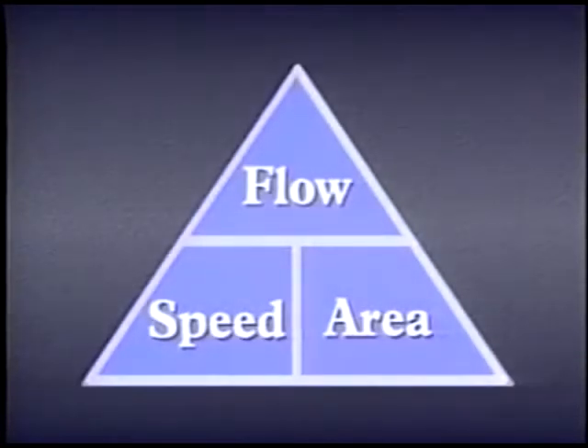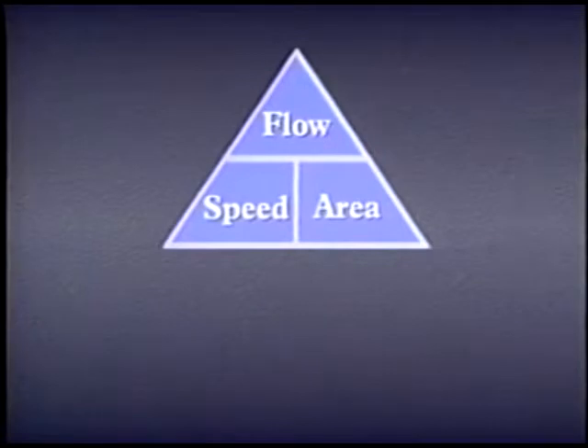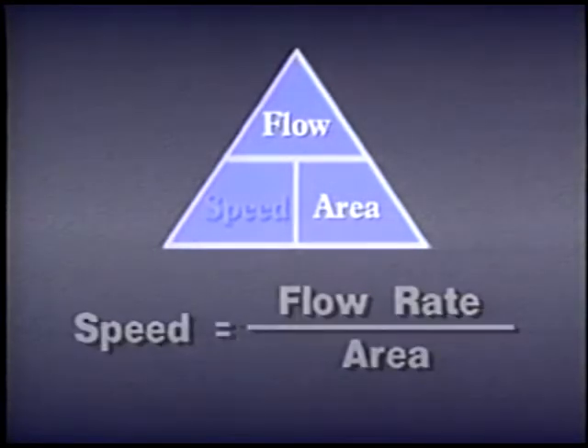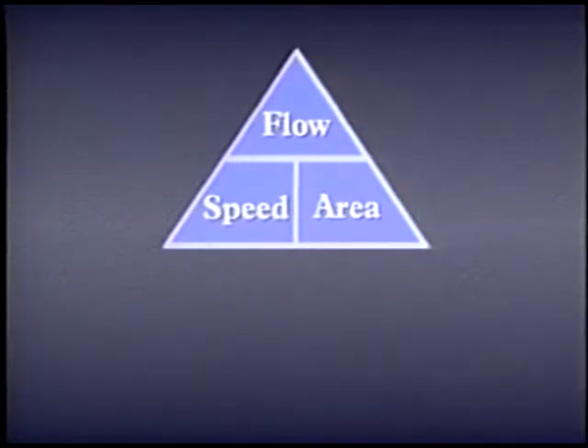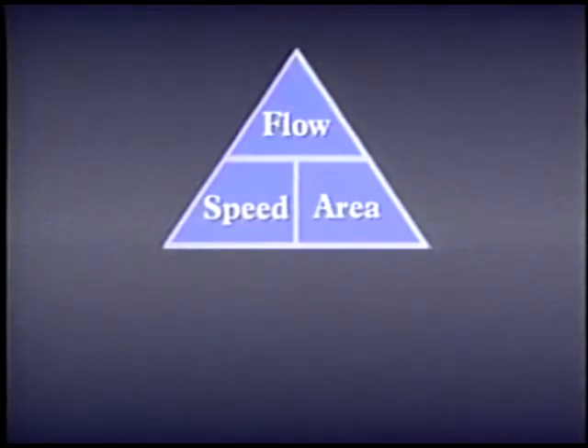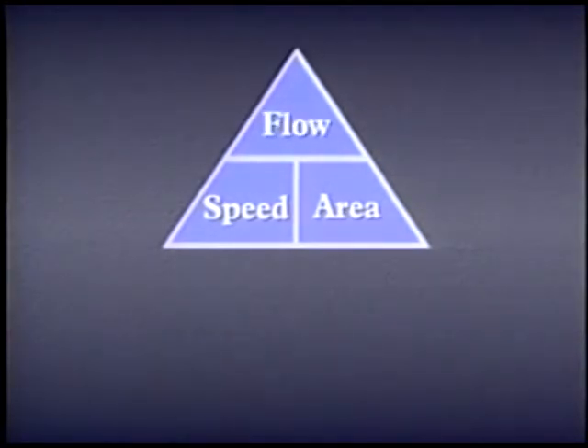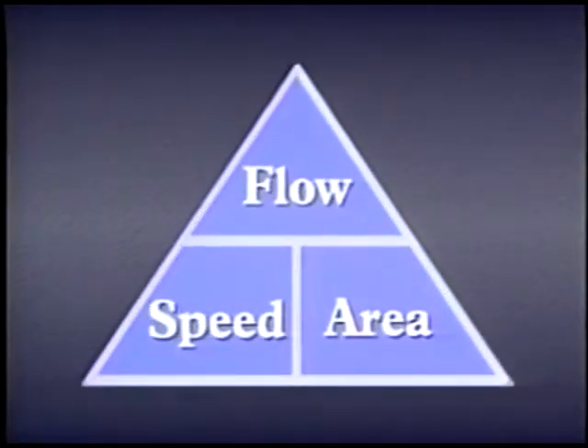We can use the same triangle technique to remember this formula. If we want the formula for speed, we cover speed and see that speed equals flow rate in cubic inches per minute divided by area in square inches. If we need to find what size cylinder achieves a specific speed at a particular flow rate, we cover area and divide flow rate by speed. Or to find what flow rate produces a certain speed, it's speed times area. Remember that flow rate in cubic inches per minute is at the top of the triangle.